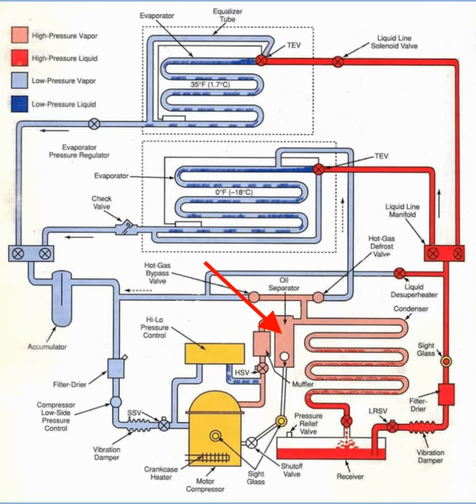The oil separator separates oil from the high-pressure refrigerant coming from the muffler. There are a couple of types. The first, the helical type, uses a centrifugal vortex action causing the refrigerant to spin inside the separator.